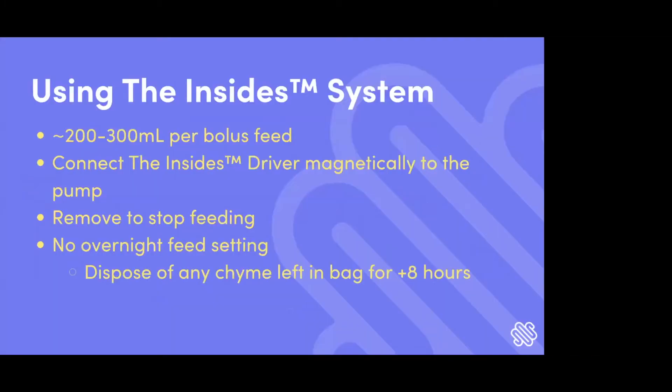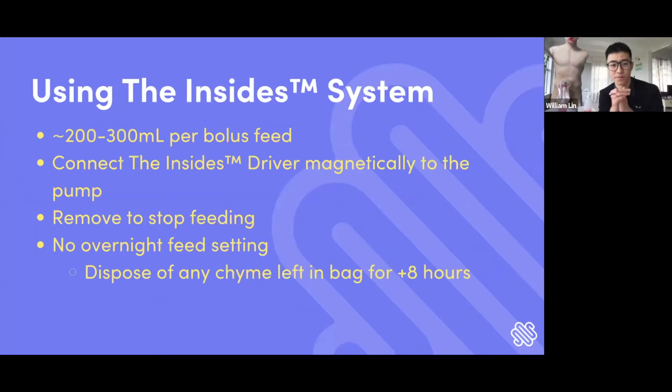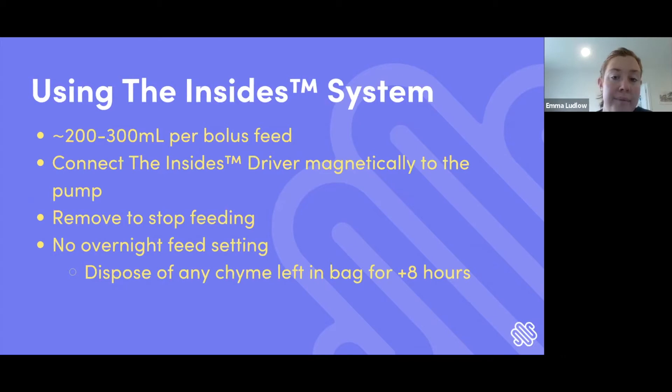To summarize: with the Insides system, a bolus feed for a patient is between 200 to 300 ml, or whatever their ostomy bag can hold, and it's not too heavy for them. You magnetically couple the driver while it's turned off to the pump and then turn it on. To stop refeeding once the bag is empty, you just pull the driver away and then turn it off. We only have bolus feeding at the moment, so patients do need to wake up in the night to bolus feed. We currently don't have a continuous setting.